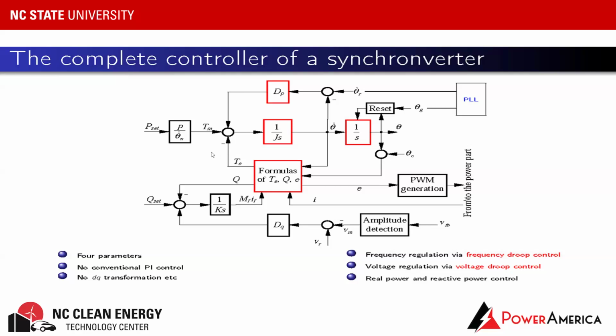And then we can just convert the real power P sets into the virtual mechanical torque TM, because the speed of the machine is more or less constant. We can simply scale this real power and use it as the virtual mechanical torque to drive the machine. So the upper part is basically the frequency droop control, because DP, the damping factor of the synchronous machine, actually plays the role of frequency droop control. So we can use that to achieve the frequency droop control.